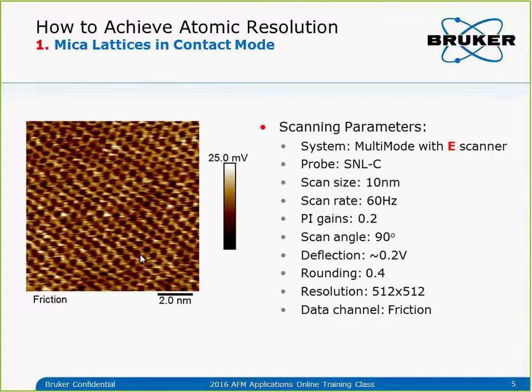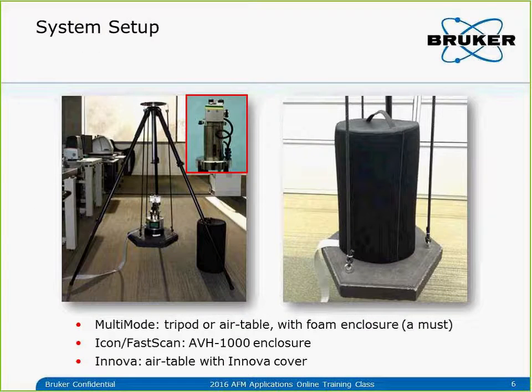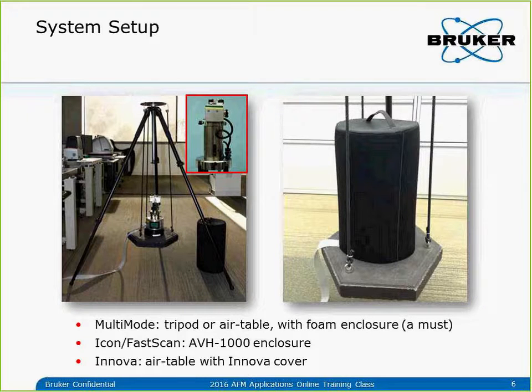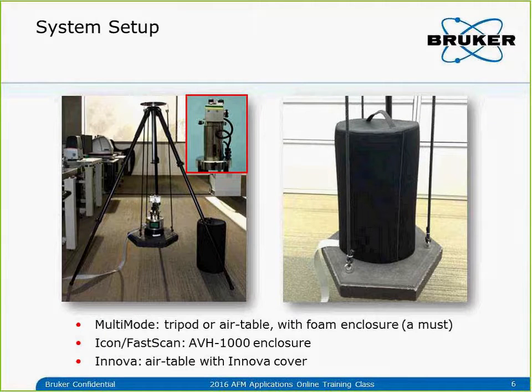Now let's go through the detail step-by-step. First we need to choose the system. ICON, FastScan, Innova, and the multimode are all capable of atomic resolution imaging. For the multimode, we need to choose the E-scanner or the A-scanner. The J-scanner is not capable — it's a good scanner, but it's not designed for this application.